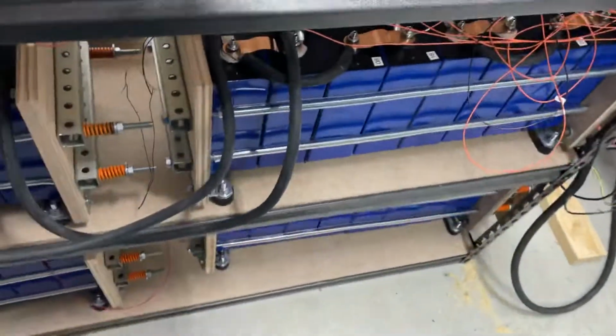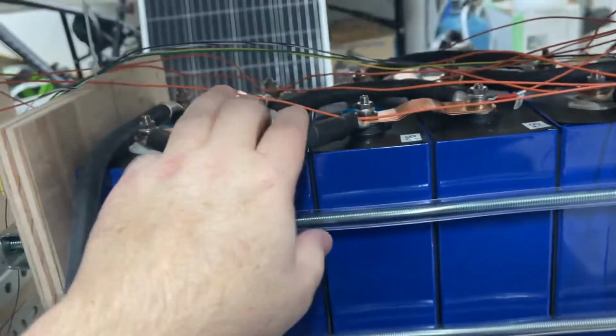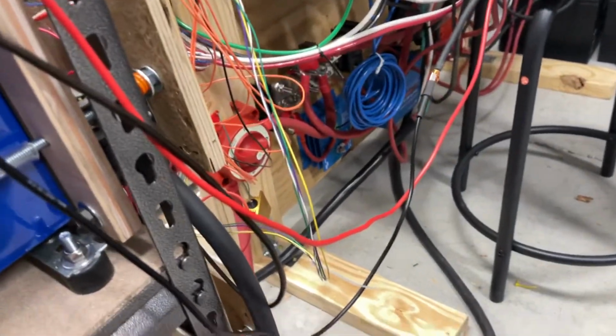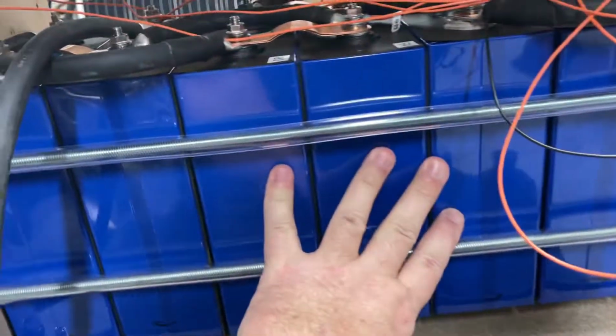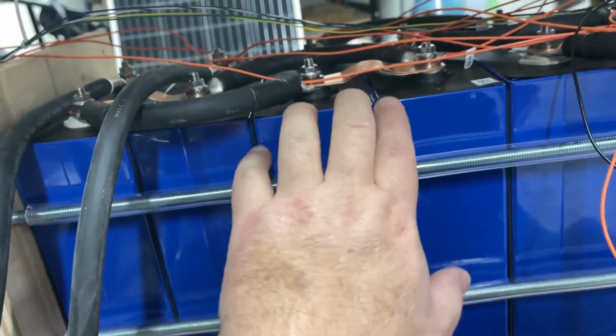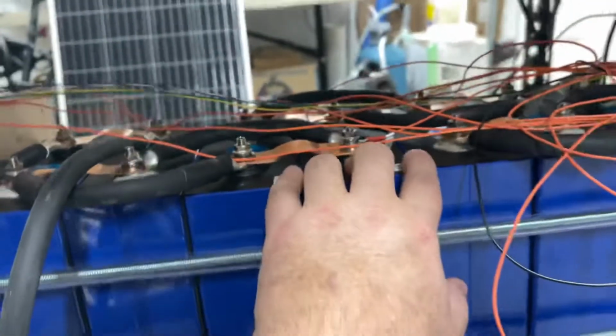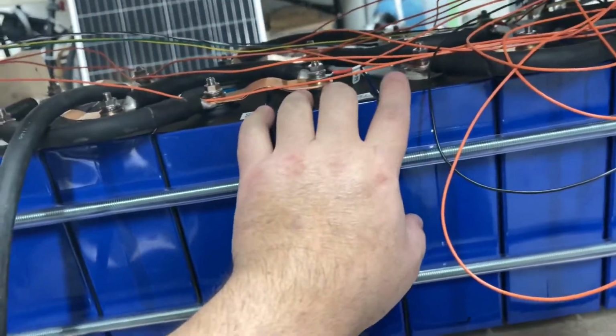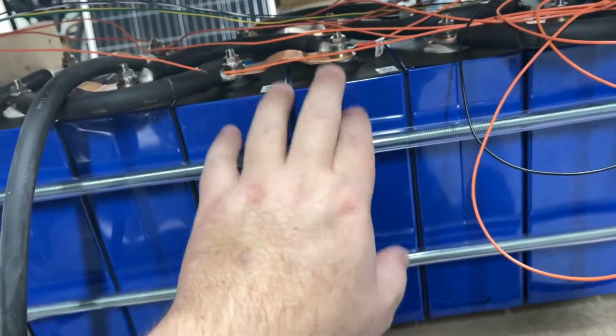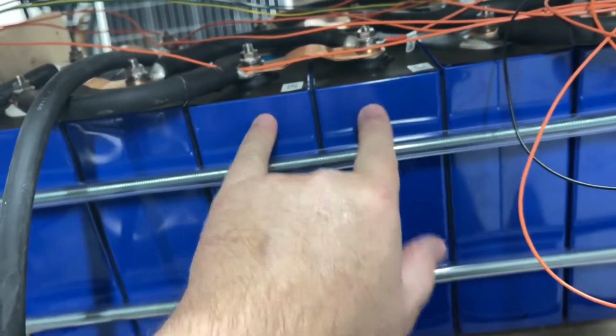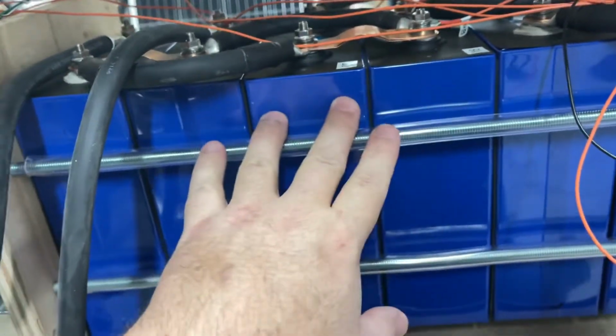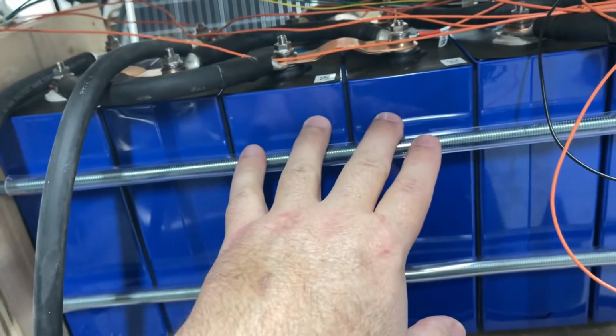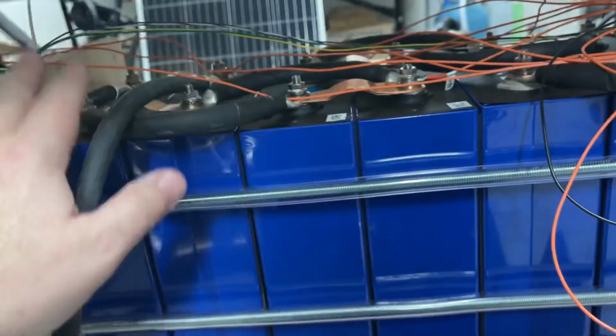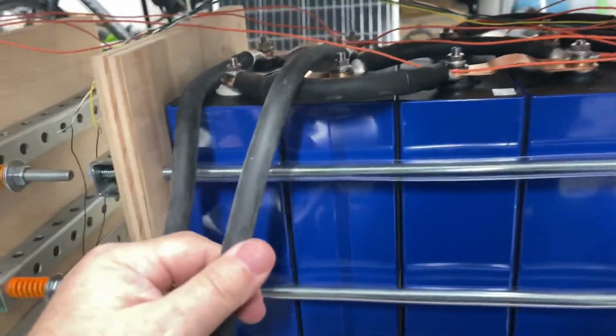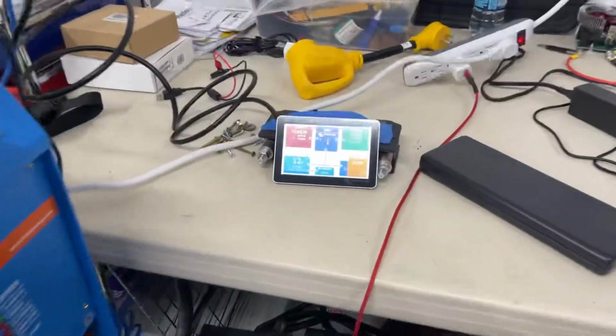So what that means is that none of these connections are receiving the full bore 140 amps, which is 0.5C for these cells. These are 280 amp hour cells, so 0.5C is actually a pretty reasonable amount of current to charge or discharge them with. Even at full charge, if I only had 16 of these cells with none in parallel, they'd be getting 0.5C. But because I have 2 in parallel, they're receiving half of that, each getting between 63 and 64 amps, so that's only 0.25C. That's really easy on these cells, really easy on the wiring. So this thing is capable of charging at 7,000 watts.